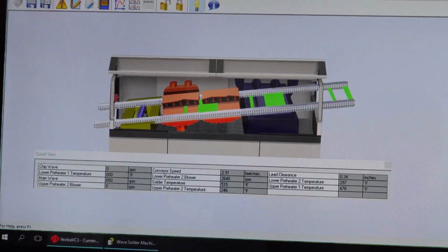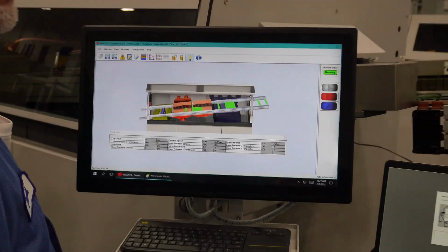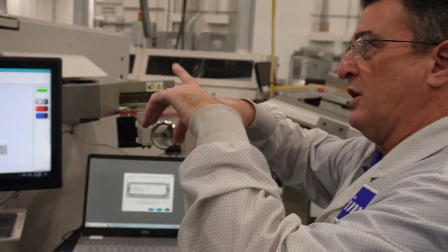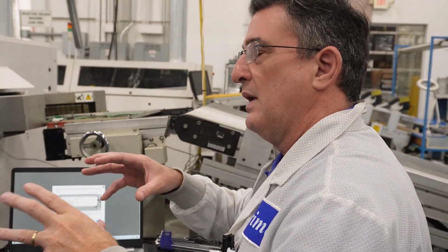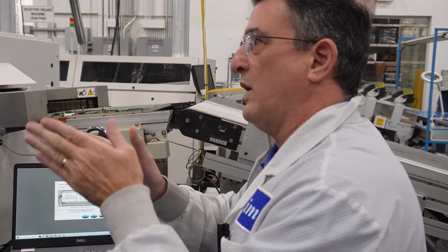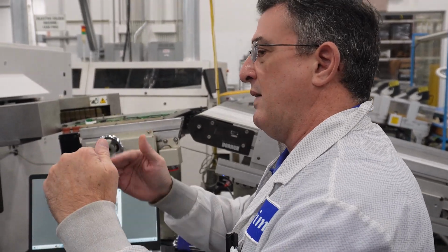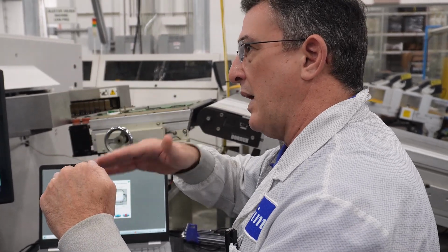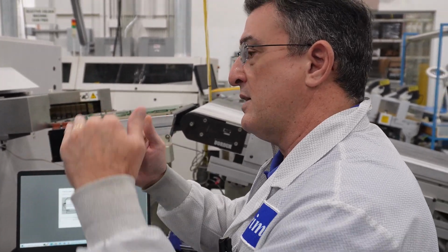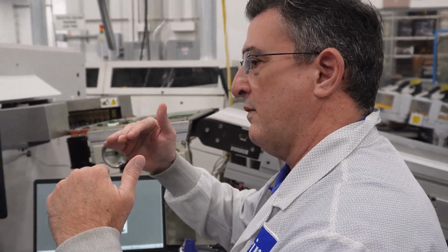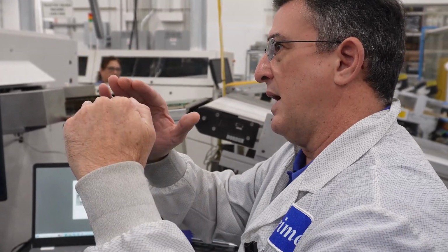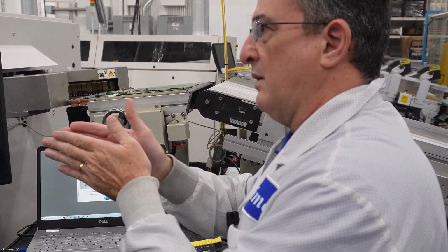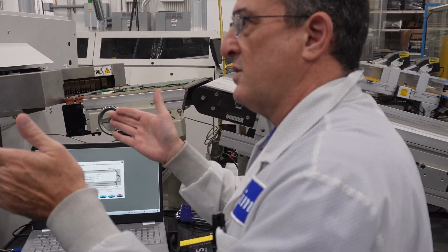Because when we lose that temperature, the software wants to know where that's at, because it's gonna do that prediction algorithm we talked about before, and it doesn't want to see a dead zone. It wants to divide that up between, because even though there's no actual forced convection going on right there, that dead zone, I call it, that gap between the two is influenced by those two different zones. If I turn this up, that gap's gonna heat up on this side, right? And so that's why we want to divide it down the middle and give half of that to the adjacent zones, okay?